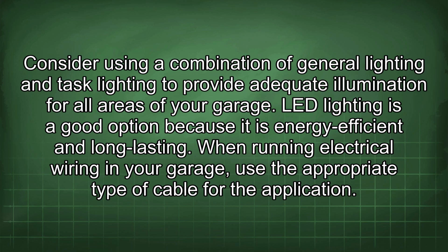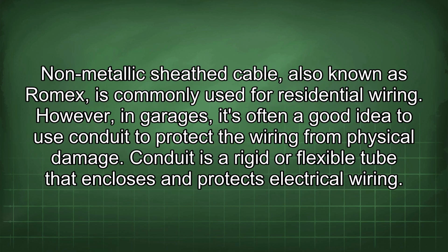When running electrical wiring in your garage, use the appropriate type of cable for the application. Non-metallic sheath cable, also known as Romex, is commonly used for residential wiring. However, in garages, it's often a good idea to use conduit to protect the wiring from physical damage. Conduit is a rigid or flexible tube that encloses and protects electrical wiring.